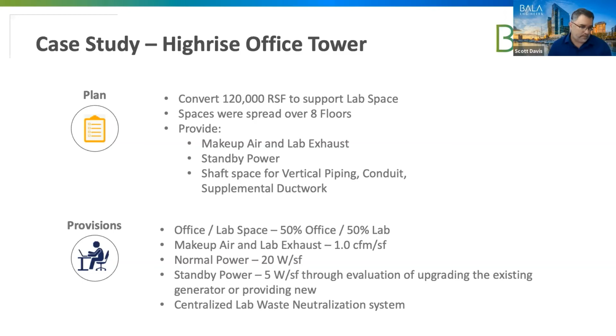Under provisions, overall, they're averaging about 50 to 50, but the first fit out we're looking at is definitely a lot higher on the lab to office ratio. So it's going to vary floor by floor. As I mentioned, we're about 1 CFM per square foot on airflow. Here, just a quick note, the normal power you can see is a little bit higher than the average. Our average, I said earlier, was 15. This particular job, we are ending up with 20, but thankfully we have that power, so we're able to meet the need.